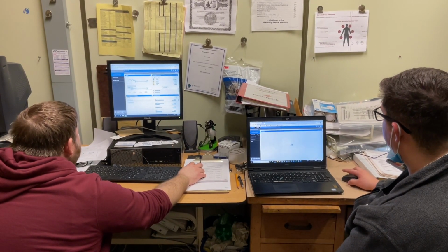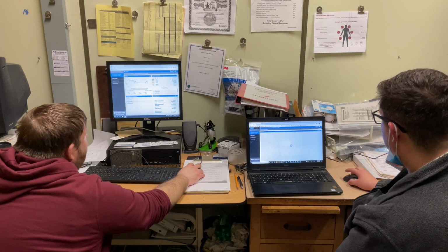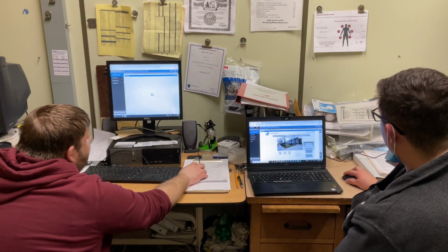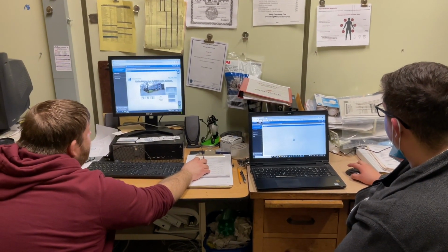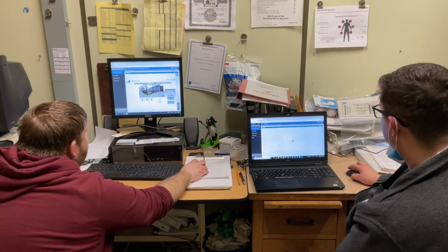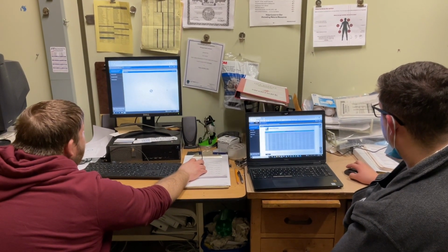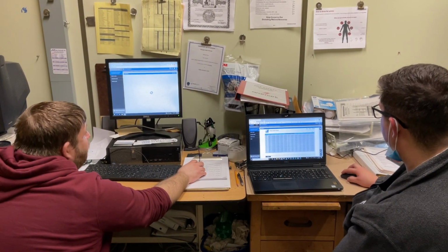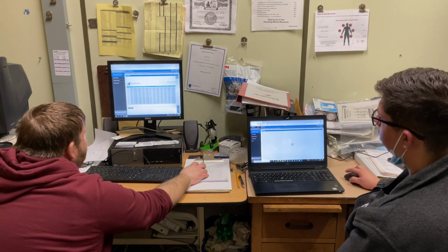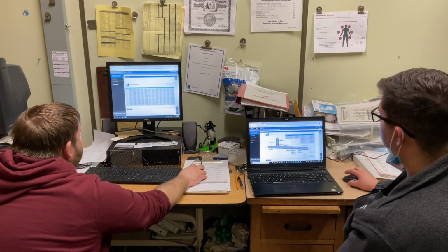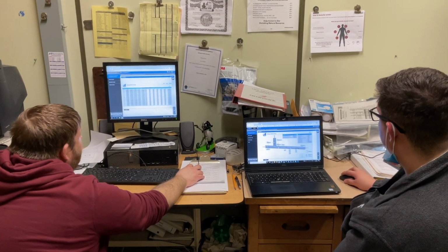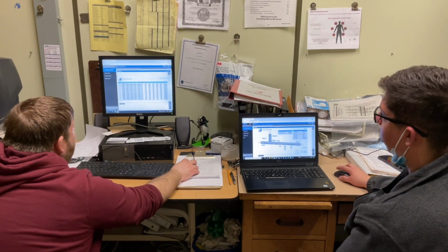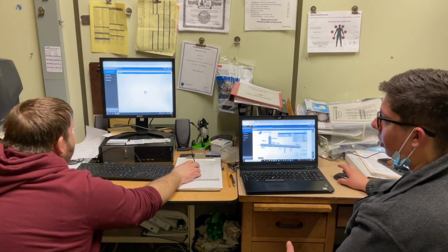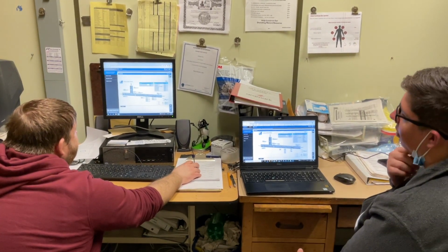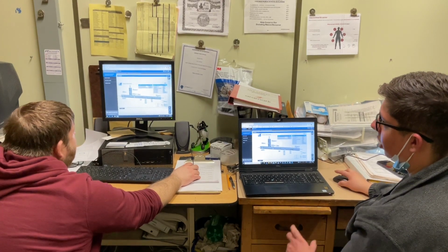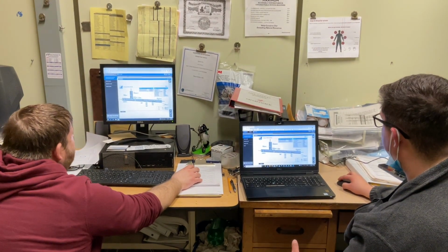So, let me go back here. Back to the unit ventilators. I just want to go over the temperature control sequence real quick. So we've talked about how the set point works, correct? Have I gone over with you how we have our effective cooling and heating set points, and how that works based on the zone temp?